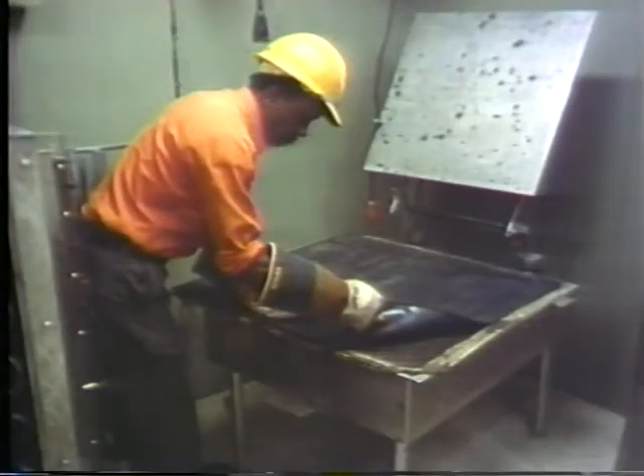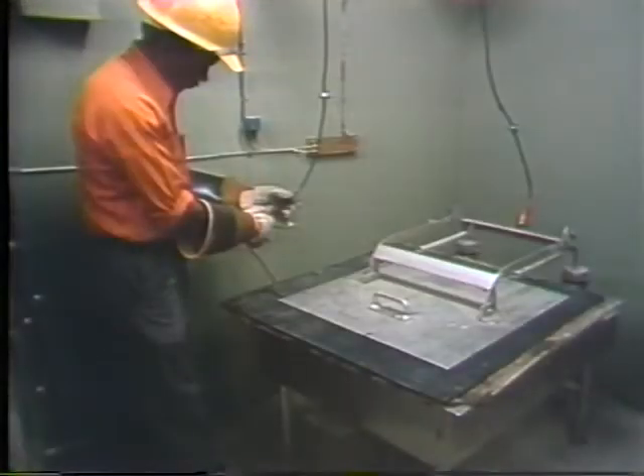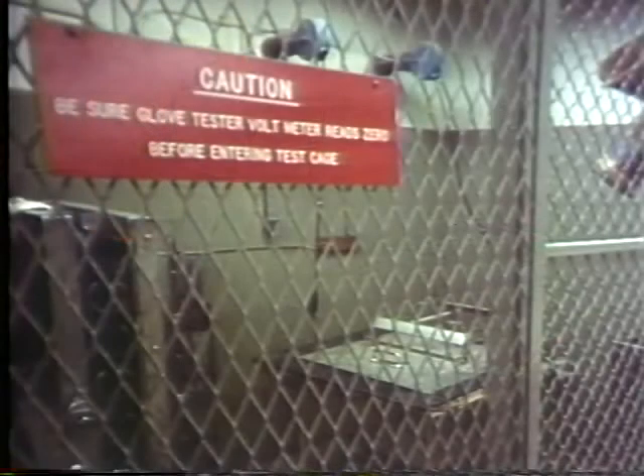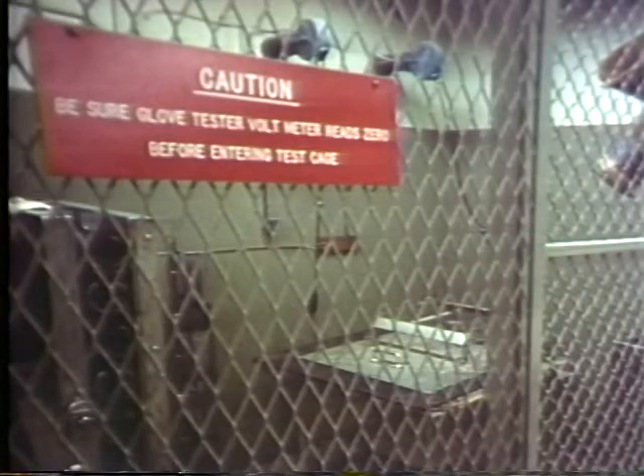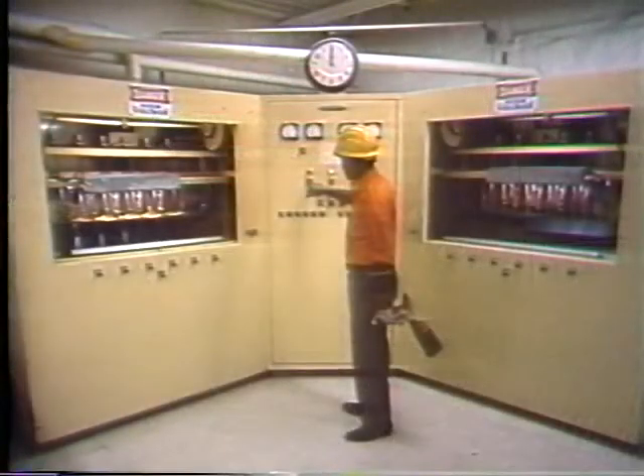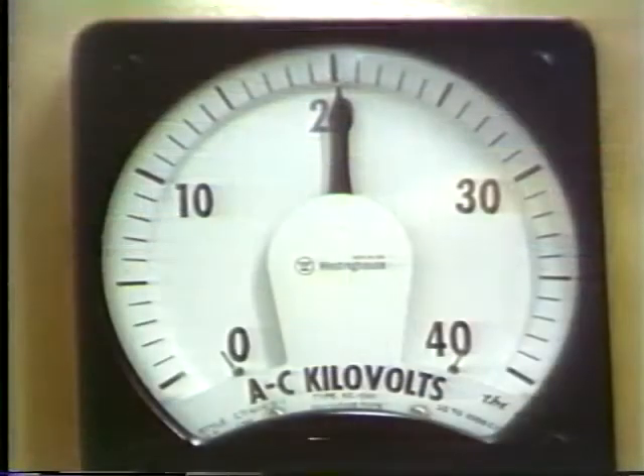Blankets and mats are tested on this device. The upper plate is connected to source, and the table is hooked to ground. For safety, the technician leaves the test cage before energizing the device. Then he passes 20,000 volts across the blanket, and if the voltage holds at 20,000, the blanket passes the test.